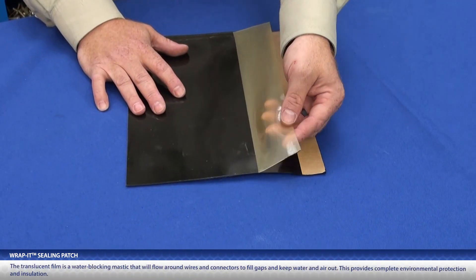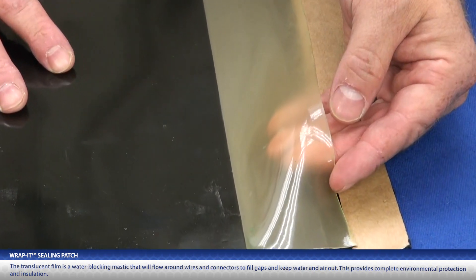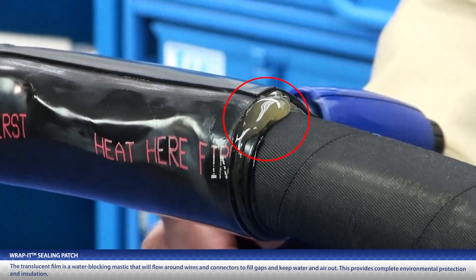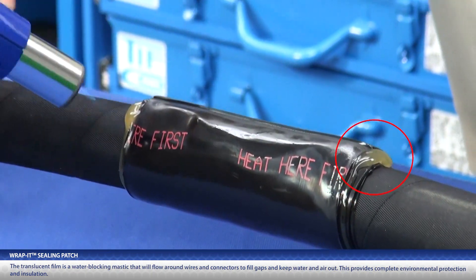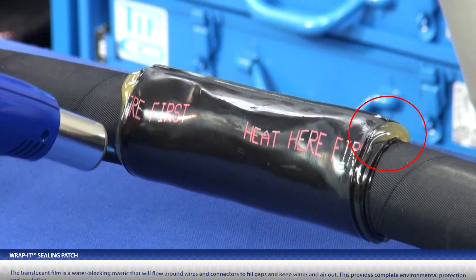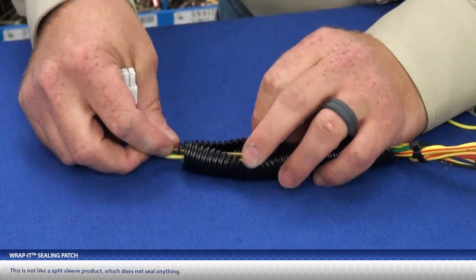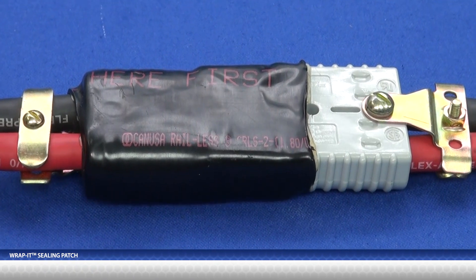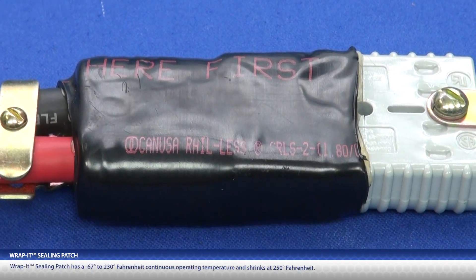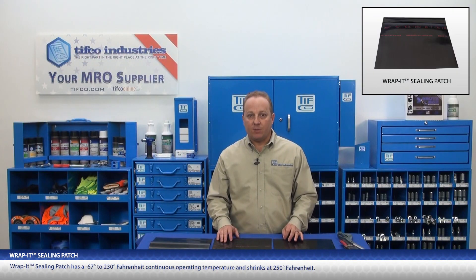Notice this translucent film. This is a water blocking mastic that will flow around wires and connectors to fill gaps, keeping water and air out, which provides complete environmental protection and insulation. This is not like a split sleeve product, which does not seal anything. The 3 to 1 heat shrink ratio even covers irregular shapes. Wrap-It Sealing Patch has a negative 67 to 230 degree Fahrenheit continuous operating temperature and shrinks at 250 degrees.